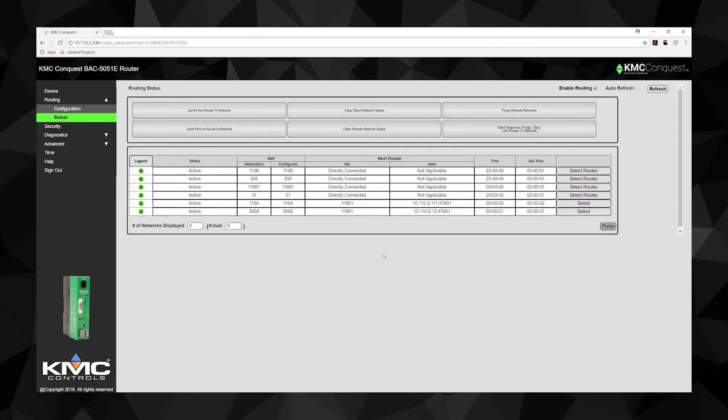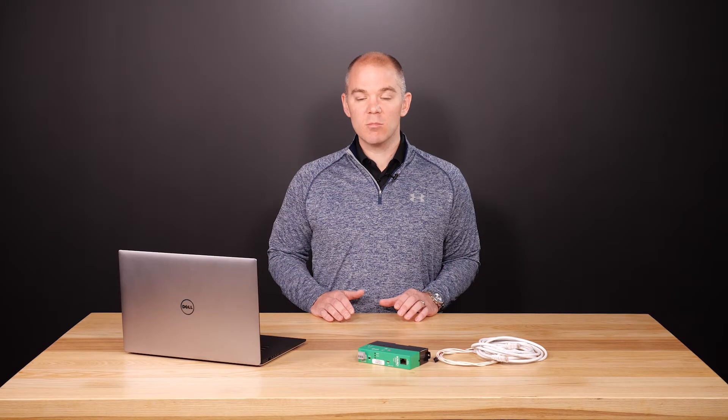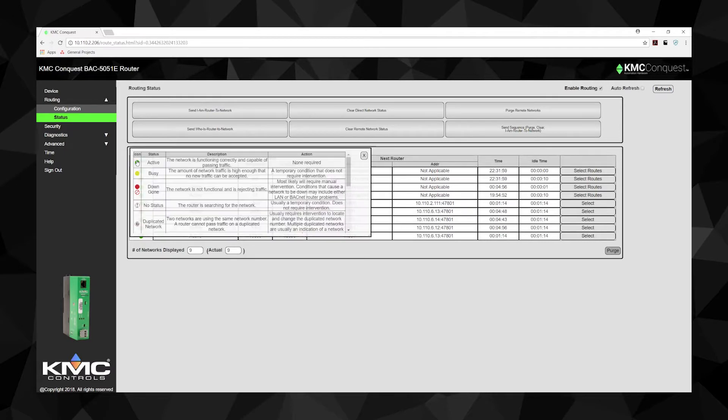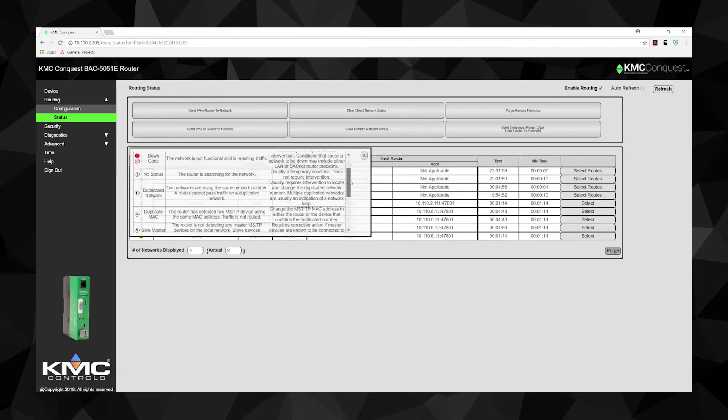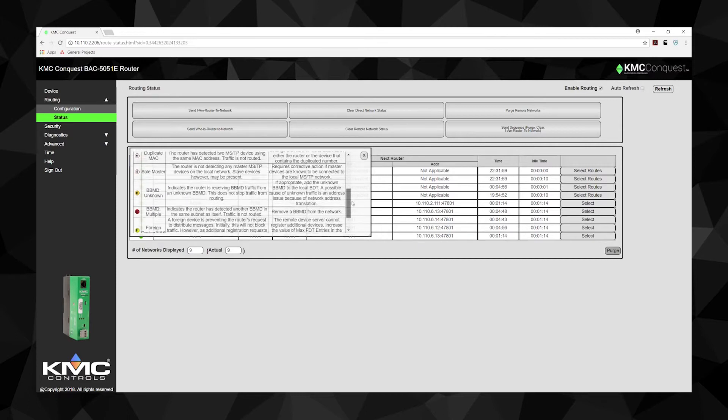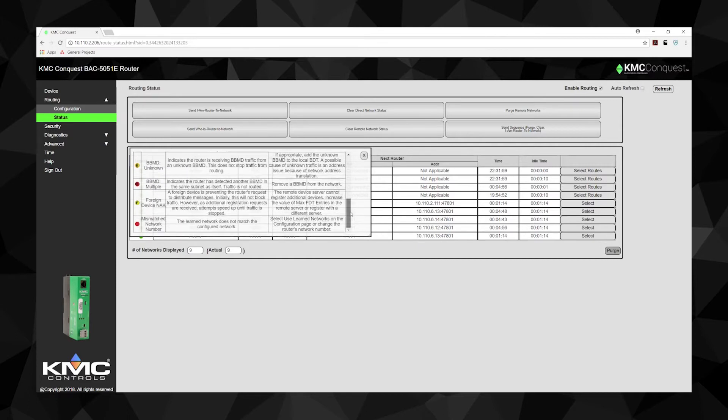The routing status table is a quick and easy way to evaluate network topology and other routing issues. A properly functioning network will have a green icon in the legend column. Yellow means the network is busy, but no additional intervention is needed at this time. There are a variety of icons indicating network errors, which can be reviewed by clicking the legend button — a window will open showing a description of the error and the actions needed.